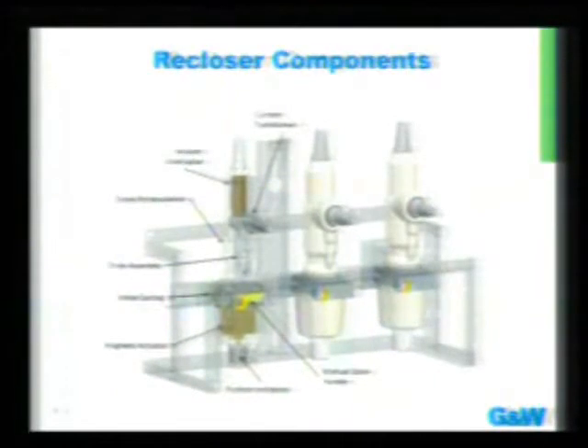Moving on to the recloser itself, this is a brief anatomy of it. As we saw in the first picture, this is the entrance of the power. It goes into this connection or bushing, then through this interrupter, which is an open and close point, and out through the other bushing to another conductor that facilitates the routing of power.